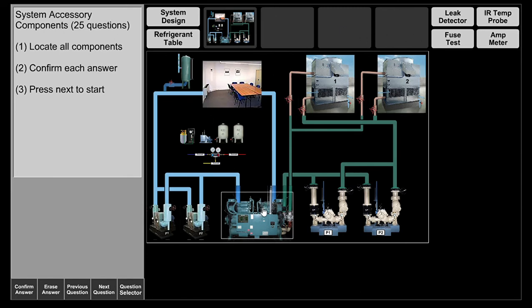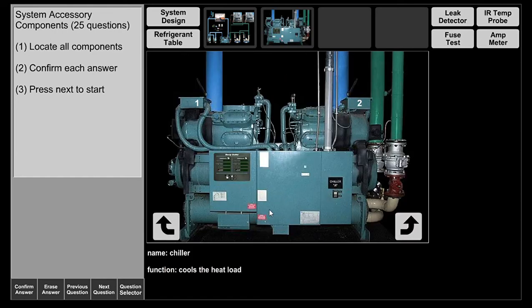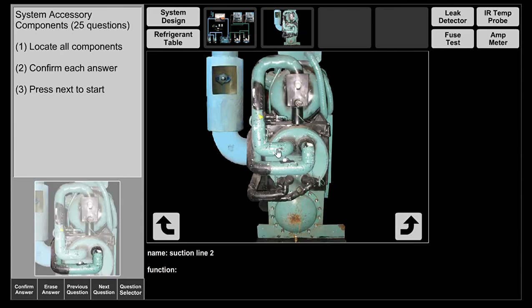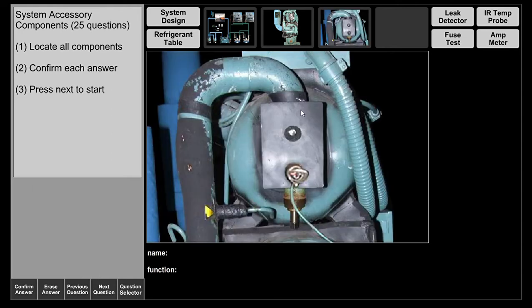Now let's discuss the reciprocating chiller itself. The basic components of refrigeration are present: compressor, evaporator, metering device, and condenser. Chilled water comes in and the low pressure, low temperature liquid refrigerant picks up the heat, evaporating into a low pressure, low temperature superheated vapor. Once in vapor form it exits as a vapor and goes into the suction line toward the compressor.